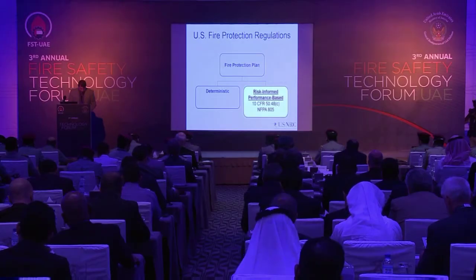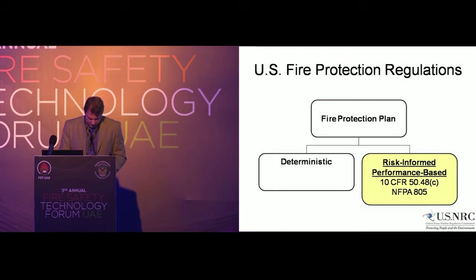This regulation permits licensees or utilities to voluntarily adopt a risk-informed, performance-based fire protection program. The risk-informed, performance-based approach considers risk insights as well as other factors to better focus attention and resources on design and operational issues according to their importance to safety. This approach relies on a required outcome rather than a specific process or technique to achieve that outcome. It allows utilities to focus their fire protection activities on the areas of greatest risk.